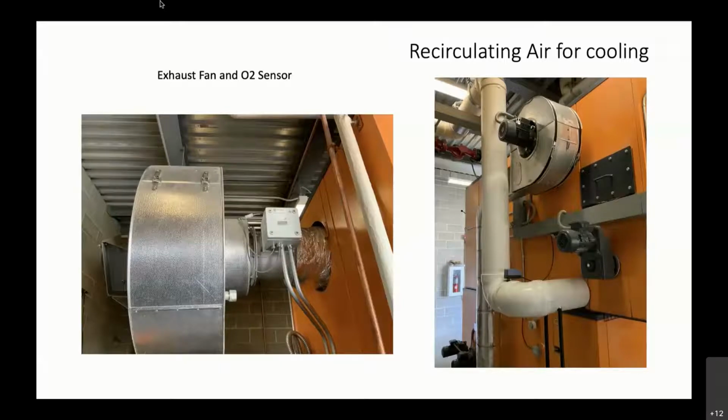Once you go over 750 or 800 C, then you're making glass in there. And the ash fusion temperature is right around 800 or 850 C. And so what we have noticed, anybody that really supplies flue gas recirculation can control that tightly. They do a really good job with complete combustion. You get very good ash content, you get very good efficiency overall, and good results. And then all your maintenance goes down as soon as you can control the overheating of the combustion chamber.